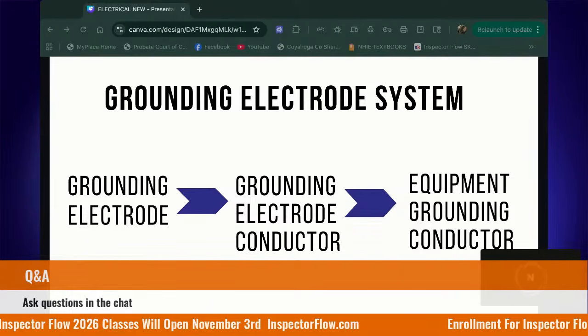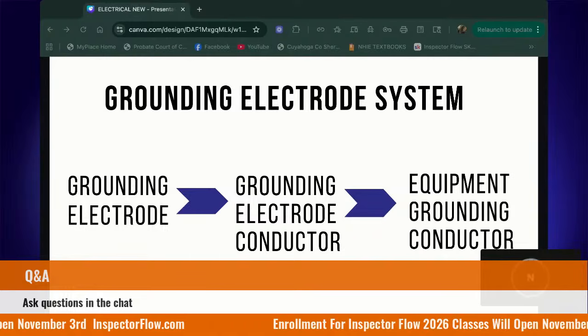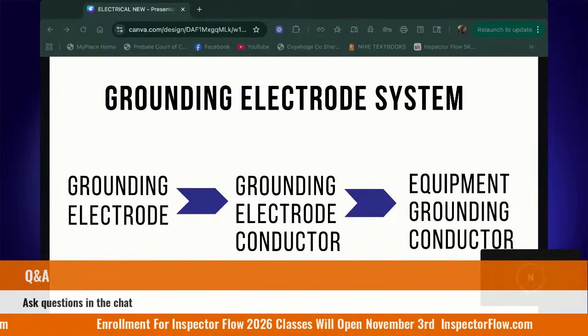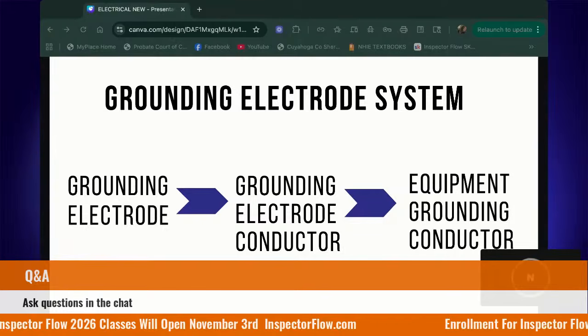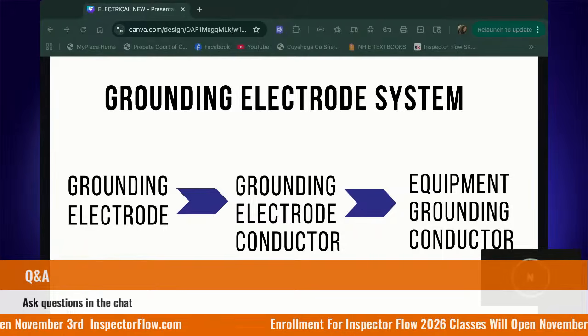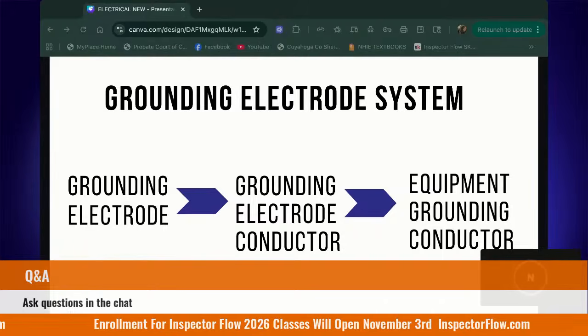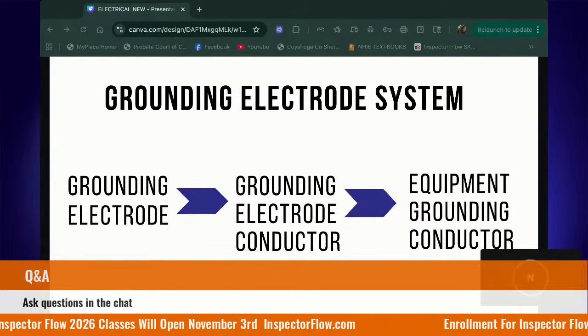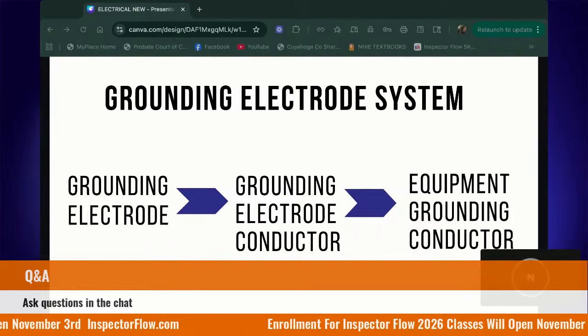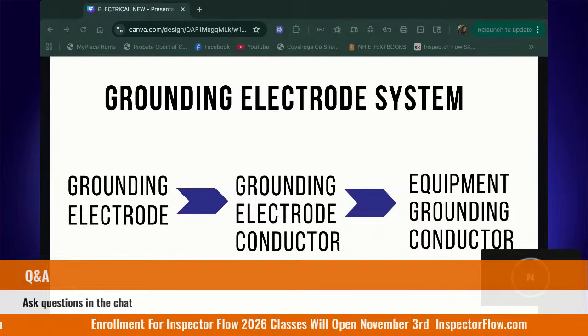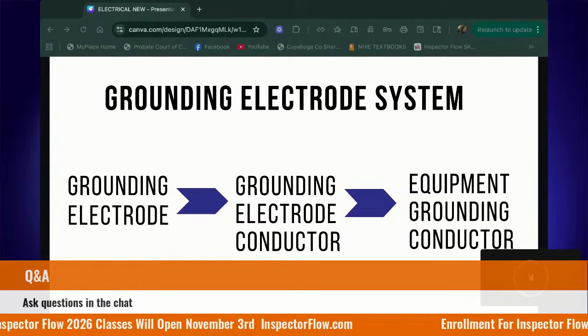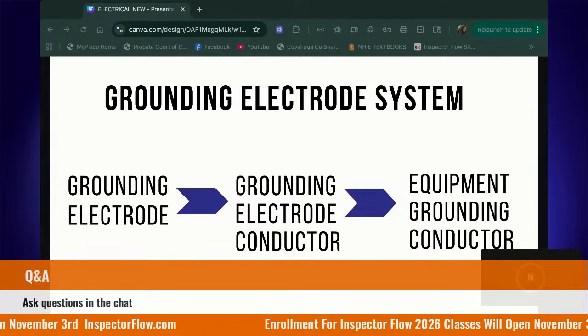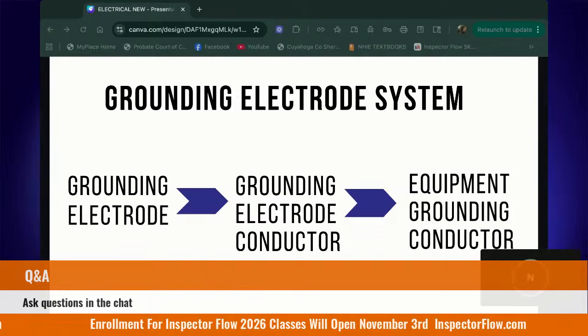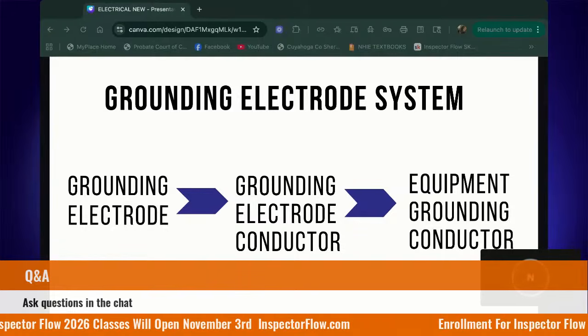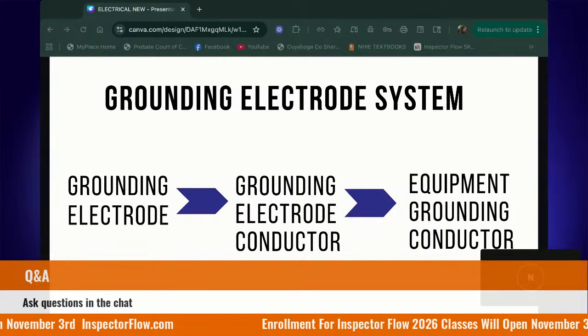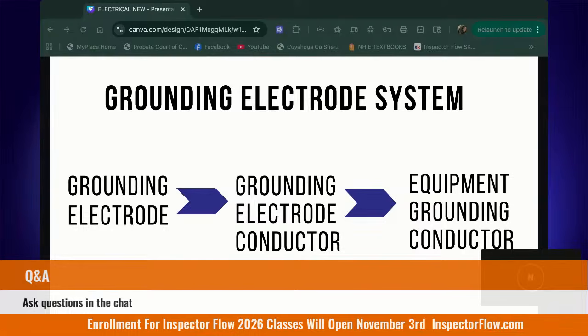Okay, because remember, our GEC will connect the panel to the GE. But don't we need grounding protection at our receptacle, at our light switch? How would those light switches be connected to the panel that could then be connected to the GE, lest we have an equipment grounding conductor? So every time you look at a switch or a light or receptacle or whatever in your house, that load has an EGC that is connected back to the main panel. Everybody got it?